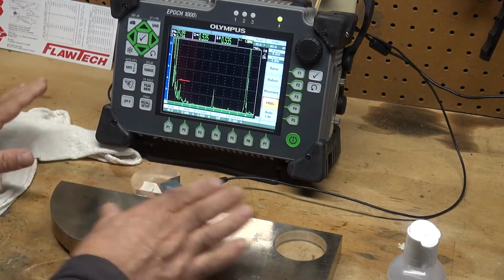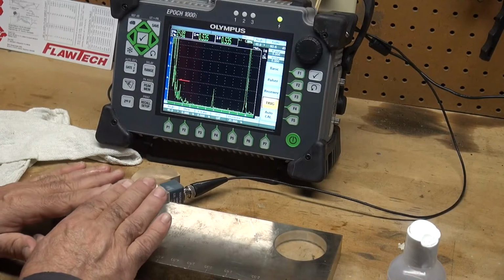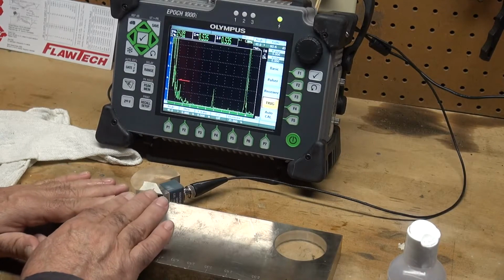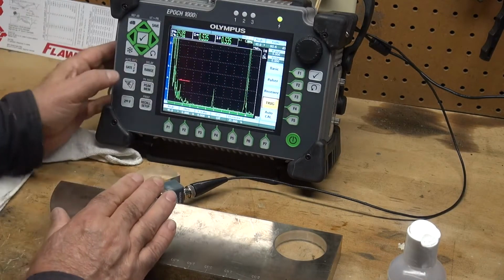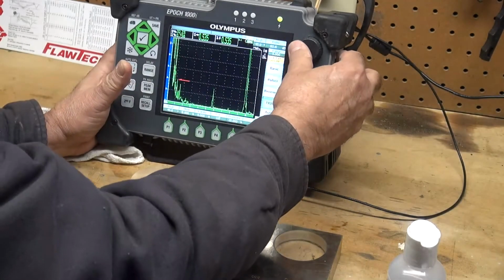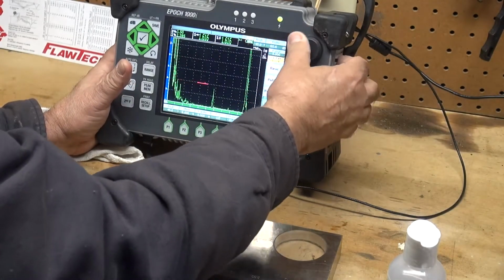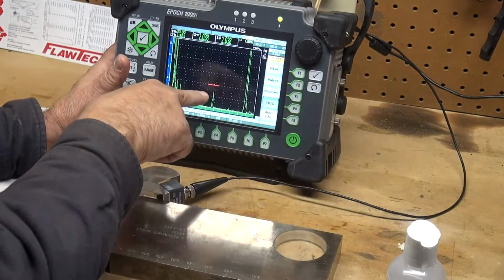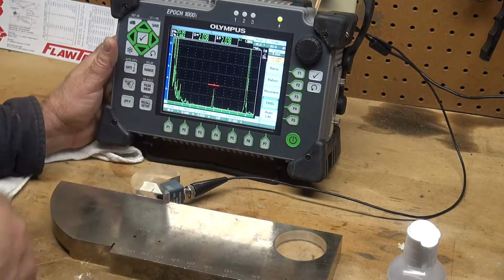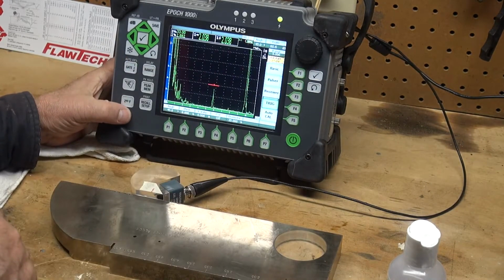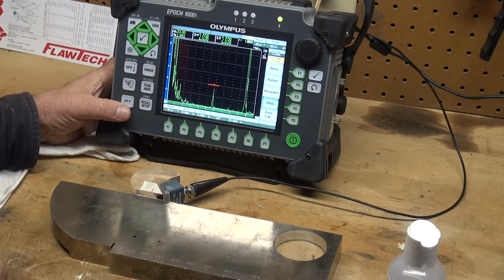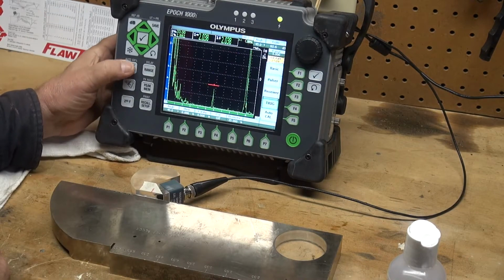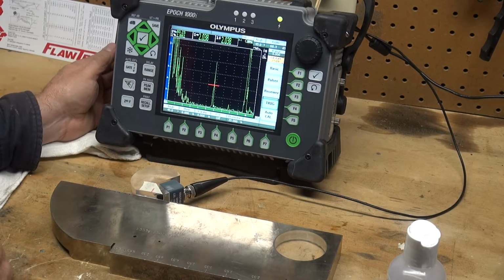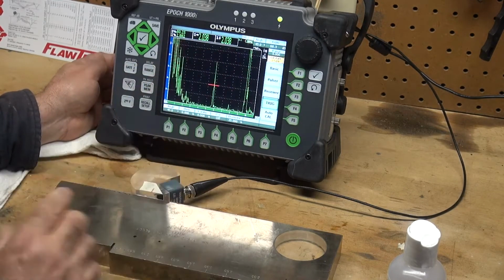So now I want to calibrate. We have this transducer in a position where I'm getting my maximum energy back. I want to take my gate, move it over that first reflector, and that's the 2 inch radius. I'm going to take it to 80% full screen height. This tester has the ability to do second function auto 80, and it'll take that signal to 80% full screen height.